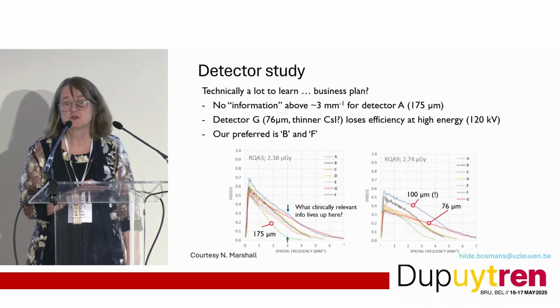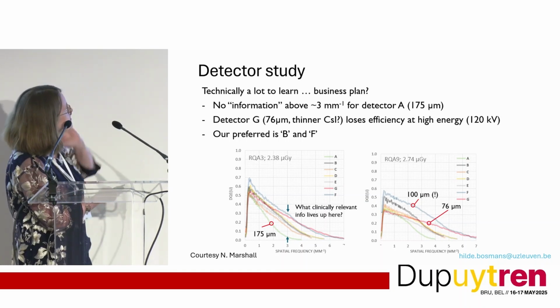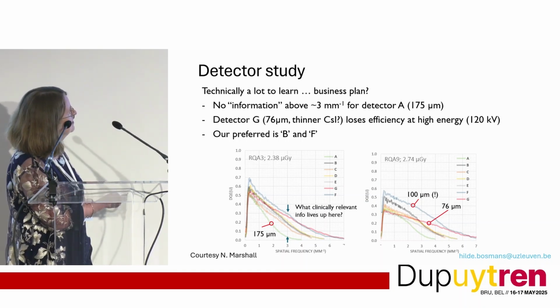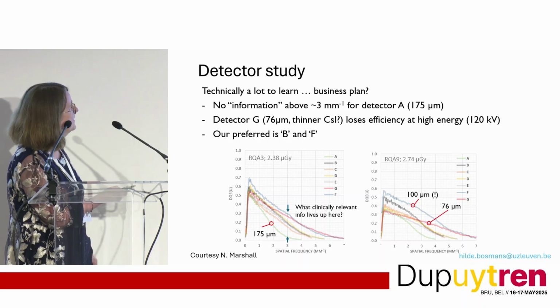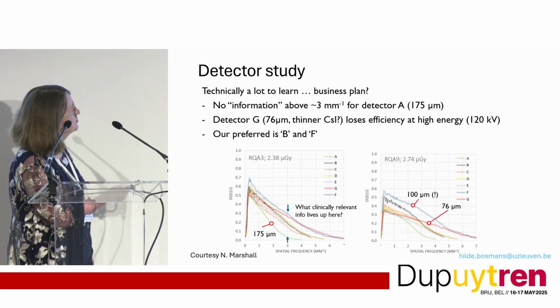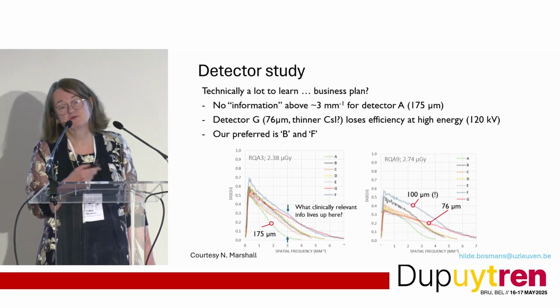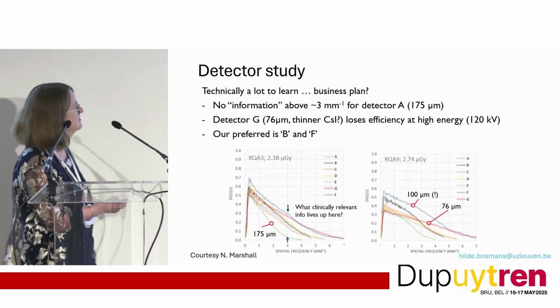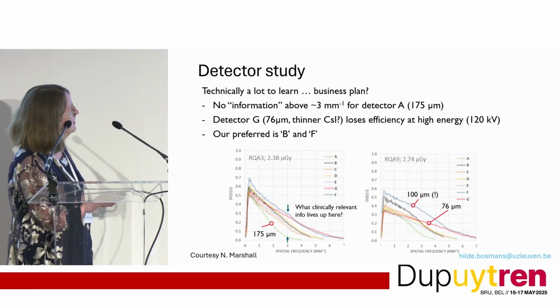And we do see differences. For instance, this blue detector here, that's a really nice one. And it wins also for the higher kilovoltages. Normally, this is what you would use for X-rays of the hand, low kV. That is what you use for the others. And then we see, for instance, the green one, really not so good.